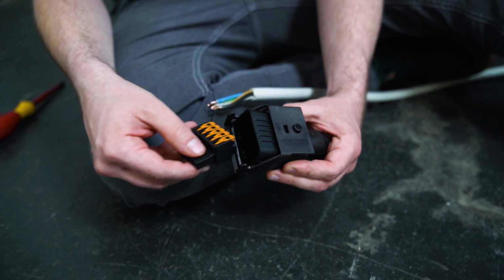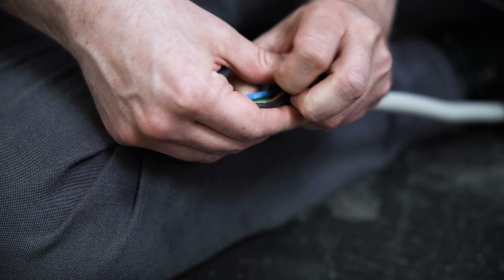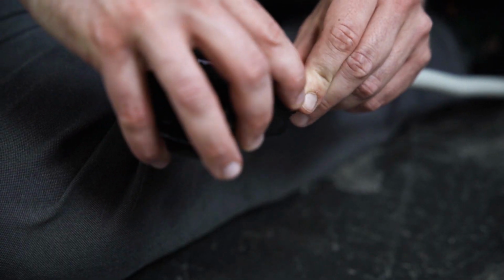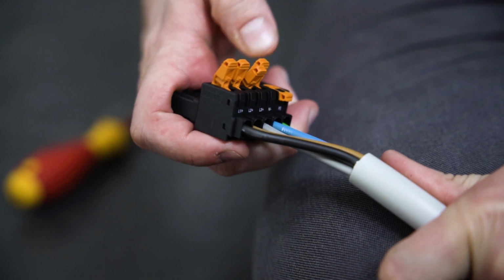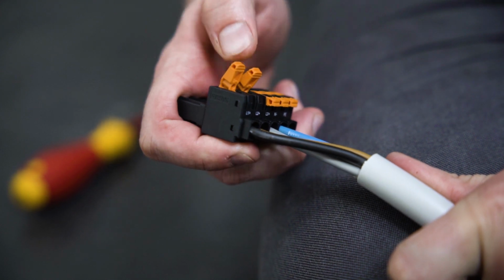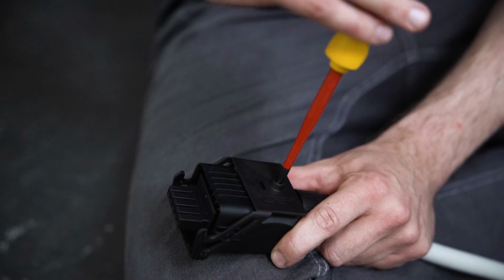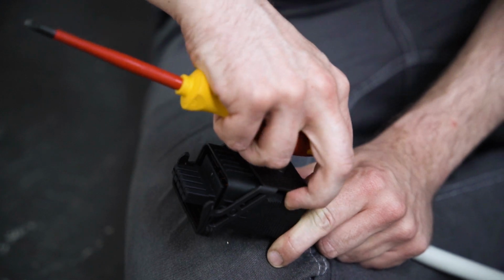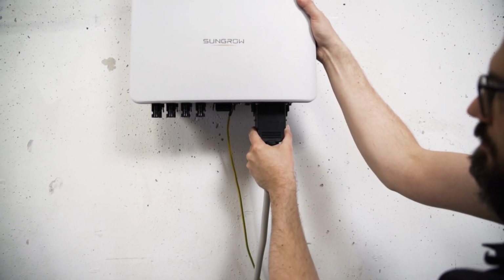The smaller versions of the new 3-phase up to 12 kW come with a newly designed AC connector. The assembly works screw-free. Only for final fixing of the connector, 1 screw is required. Quick and easy. Connect the AC connector to the inverter.